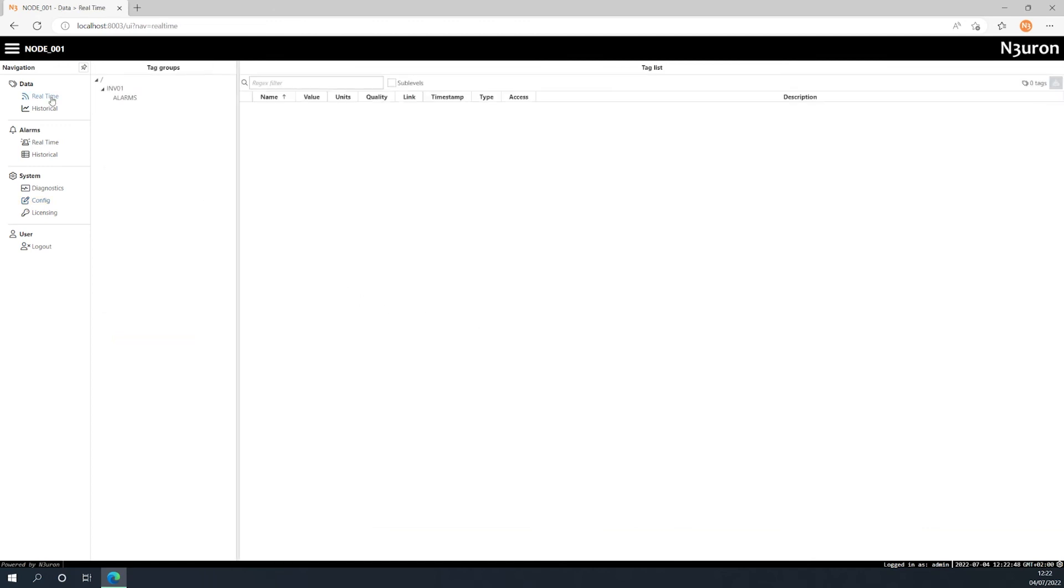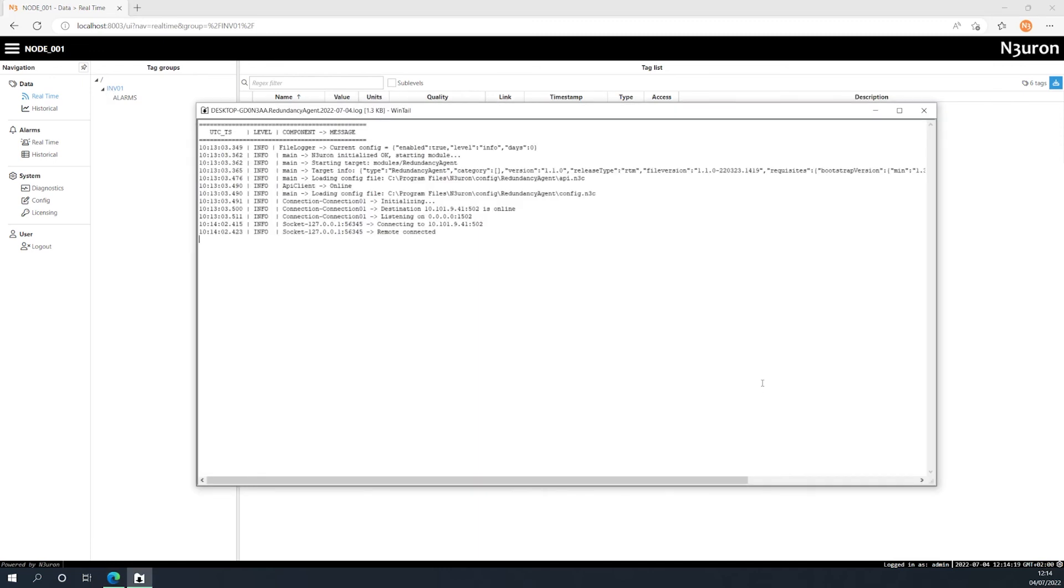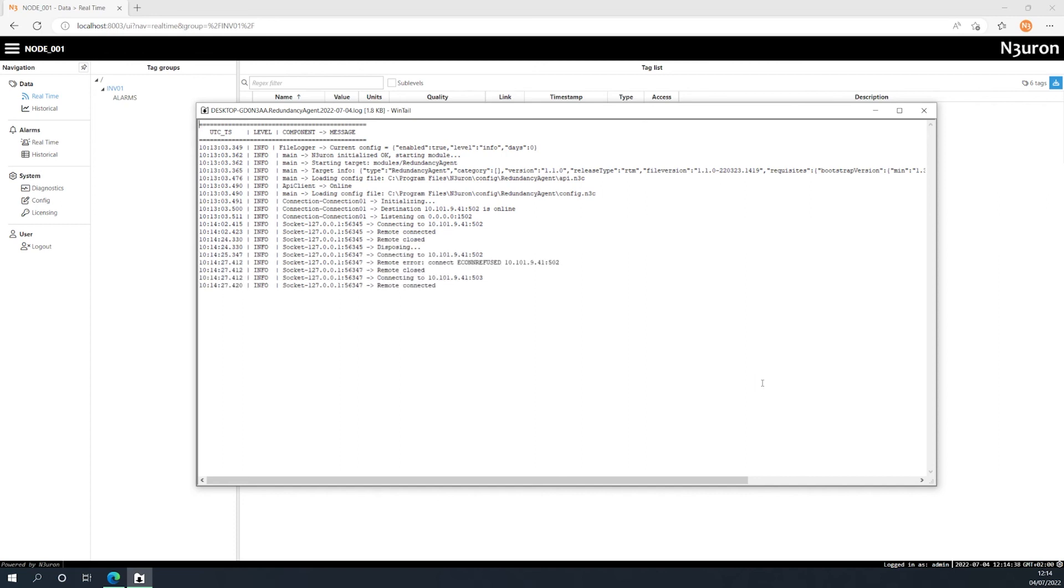Now let's take a look at the real time display. Here we can see the value of the tags in real time. Since the transition between connections is very fast we won't be able to see any changes here. Let's open the log to see what happens. Here we can see how the redundancy agent switches to the backup PLC when the primary connection fails and then switches back to the primary connection when the primary PLC is back again.